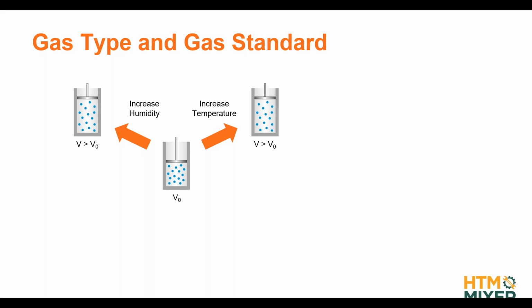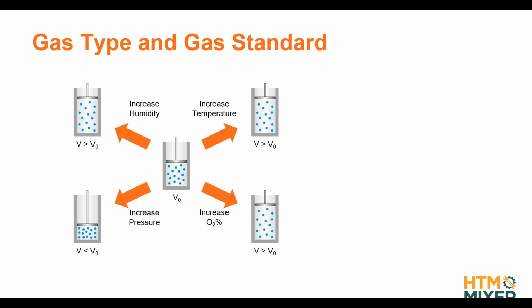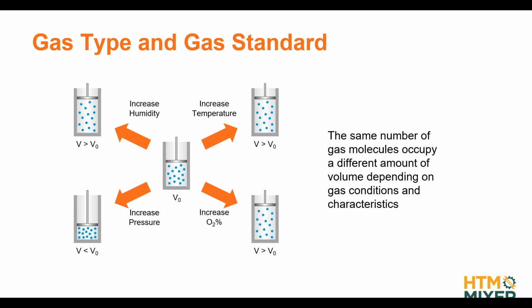What happens on the other hand if we compress, if you put pressure on the gas? It compresses, right? It occupies less volume. By the way, what happens to the temperature if we compress it? It goes up, right? So some of these things are even interconnected. And as a last example here, this is all about gas condition, but it also depends what gas it is. For example, room air has how many percentage of oxygen in there? Yeah, about 21, yeah, 20.8 something, right? So what happens if we increase oxygen concentration of that volume of air? Then it expands as well. So this means that the same amount of gas molecules occupy a different volume depending on gas conditions and gas characteristics. Okay, so that's important to understand later why we need to set gas type and gas standard on our ventilators. Does it make sense so far?